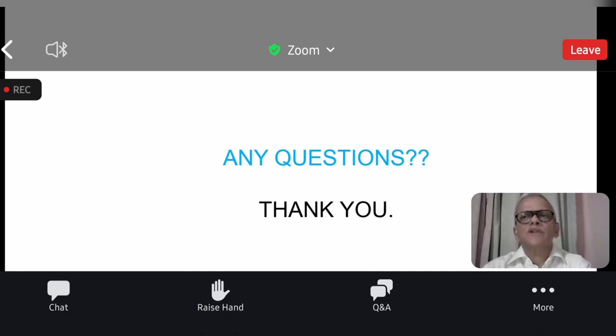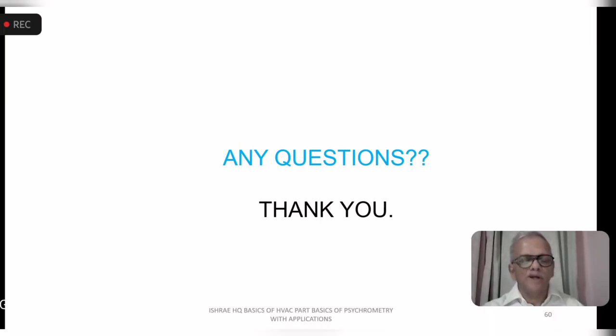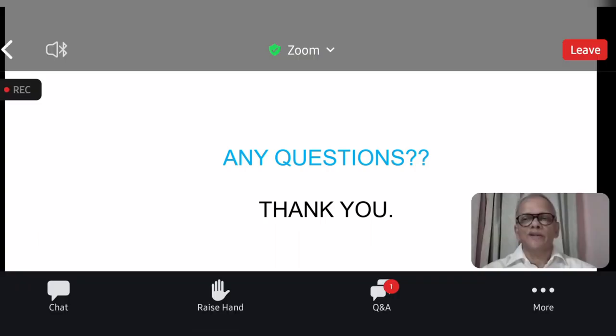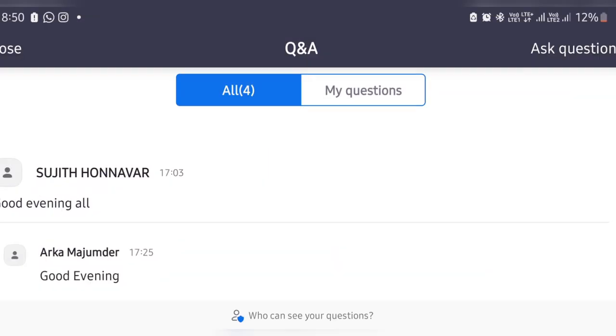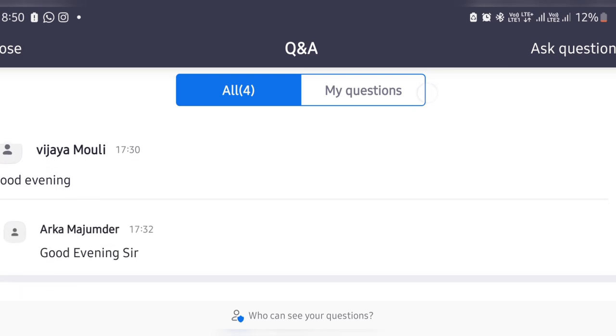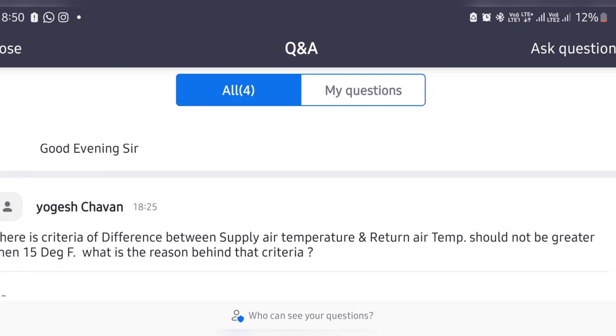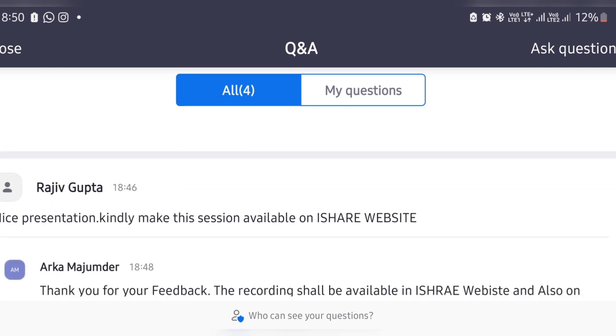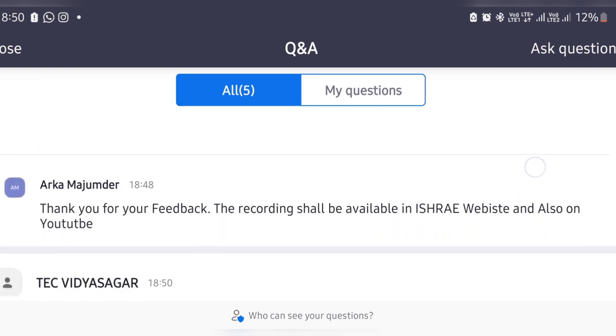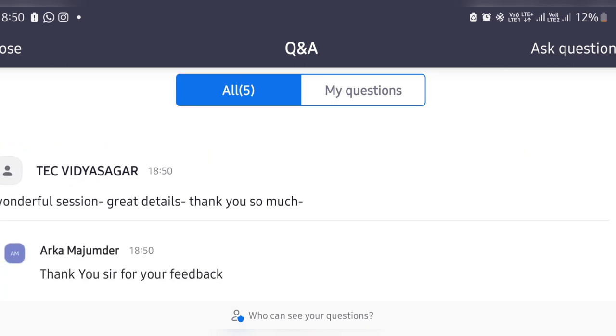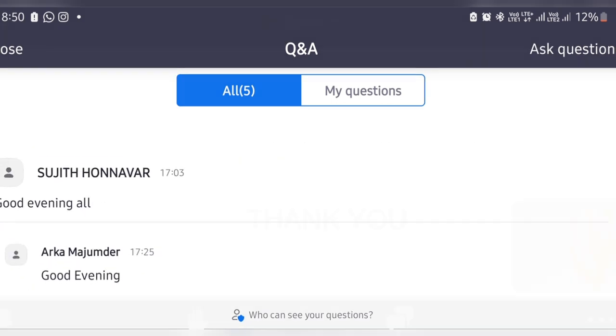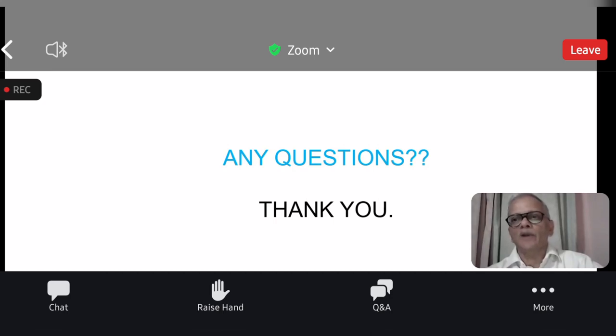I have never seen such a requirement, unless it's a specification. When we say return air, it is generally the room air, the same we are assuming that it is going as a return air. If you have a return air duct connecting the space to the air handling unit, and you are expecting some temperature rise, you allow that as a return air gain and adjust the room temperature, you add that delta T, and what is entering the coil is taken at a higher value.